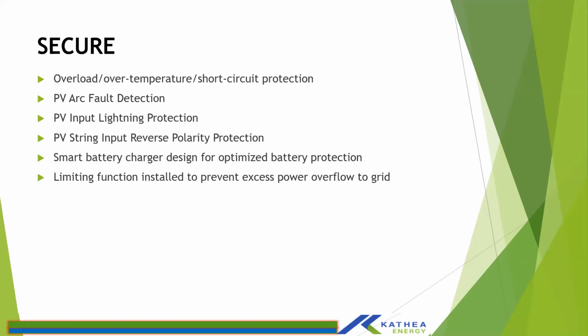Positive is terminated on positive. If you reverse polarity on the battery side, you can actually damage the inverter, and that is not covered under warranty. So please take note of that. However, for the PV array, the system comes with reverse polarity protection, but for the battery, it doesn't have that.